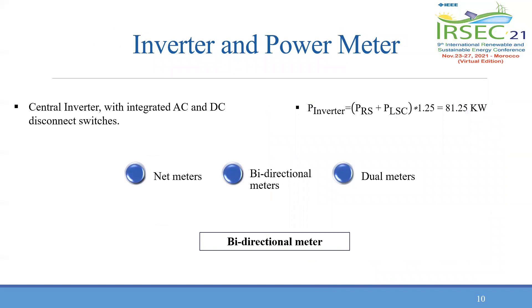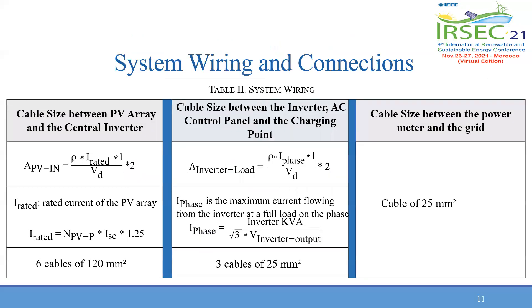The installed inverter is a central one connected to multiple solar strings and has integrated AC and DC disconnect switches. The power rating of the inverter is calculated by the equation on the slide and is equal to 81.25 kilowatts. The selected electricity meter is a bidirectional one, showing the amount in kilowatts delivered and received, the net amount, in addition to instantaneous demand in voltage and current. For wiring, copper wires of 120 mm² are used to link the PV array and the central inverter, and wires of 25 mm² between the inverter, AC control panel, and the charging points, as well as between the grid and the power meters.